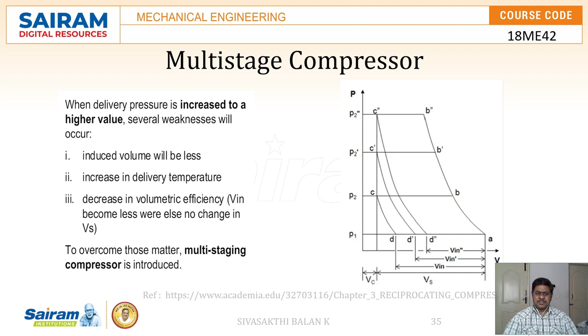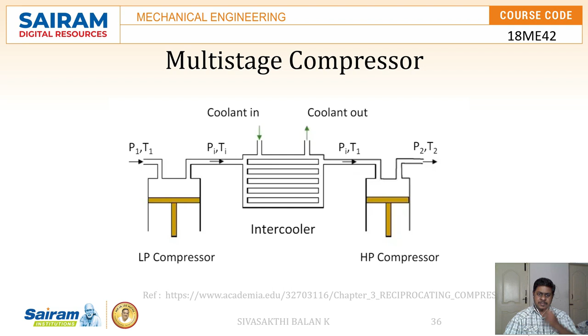To overcome all these problems or weaknesses, the concept of the multi-stage compressor was introduced. In a multi-stage compressor, instead of a single compressor which compresses to the required delivery pressure, it is divided into two compressors, first a low pressure and then a high pressure compressor. These two compressors are connected through the intercooler. An intercooler is a simple heat exchanger which decreases the temperature by absorbing the excess heat through circulating coolant. In intercooling, constant pressure heat rejection takes place. That means the pressure remains constant at the intermediate level, and only the temperature decreases to the inlet temperature, that is T1.